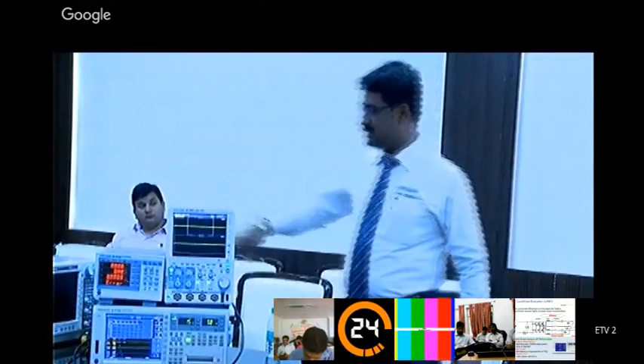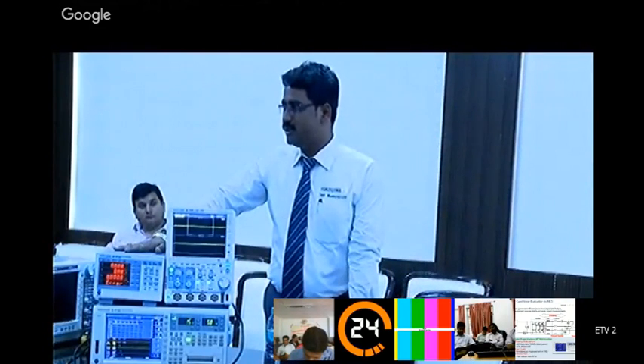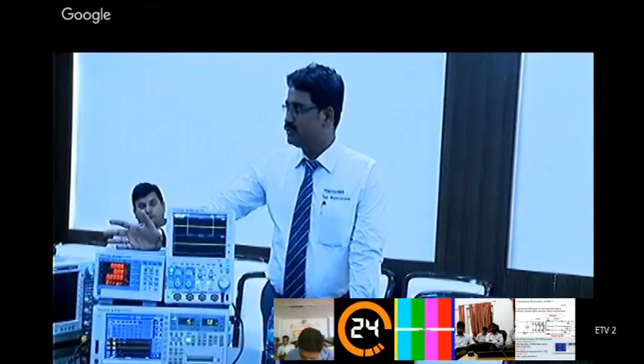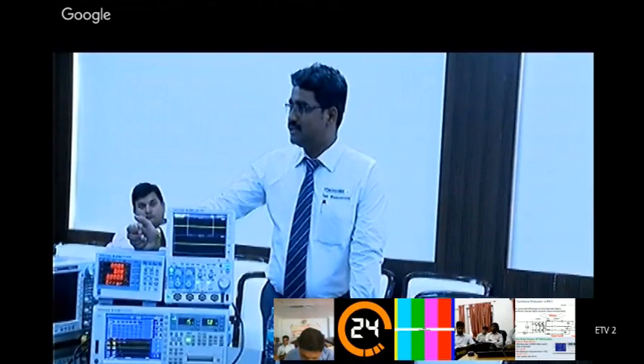The WT333 can go up to the 50th harmonic, the WT3000 can go up to the 100th harmonic, and the WT1800 can go up to the 500th order harmonic. Normally if it's an inductive load, the harmonic content will be high, sometimes even at the 100th or 150th level. For a resistive load, harmonic content is less. So depending on the loading, you can analyze the harmonics and take it accordingly.